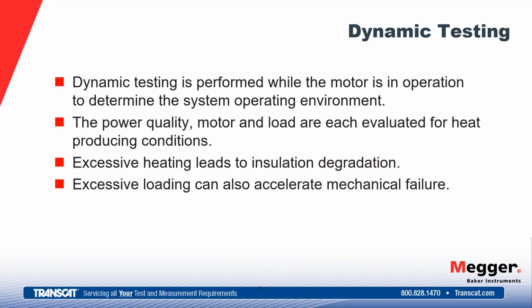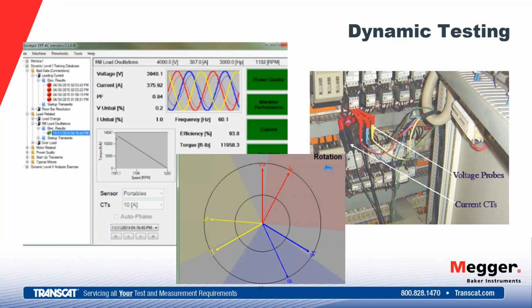Excessive loading is another item that we can see. We'll give you a load percentage, and given the nameplate information, we can determine that you're overloading this motor. Anytime you're overloading the motor, it accepts that. It's going to slow its rotor in order to produce more torque. By slowing this rotor, it's drawing more current to produce that torque. So again, we're causing excessive heat in that motor, and we're accelerating any kind of mechanical failures with that motor. We're putting more stress on the line components as we overload that motor. So dynamic testing does help us find those things.